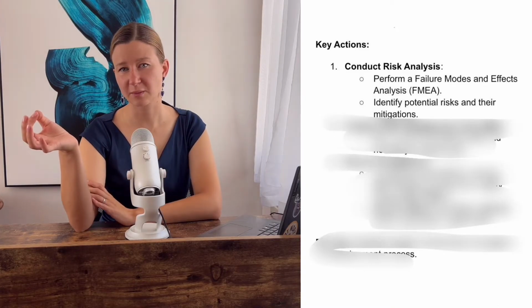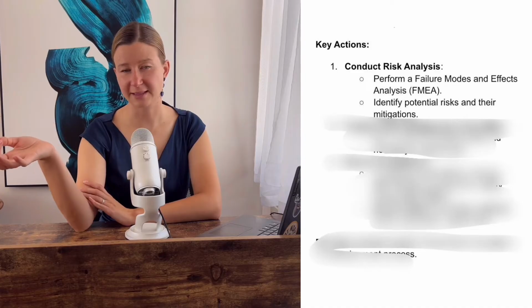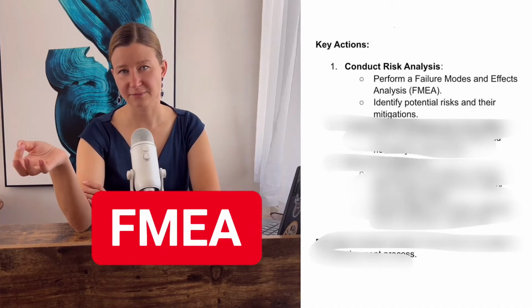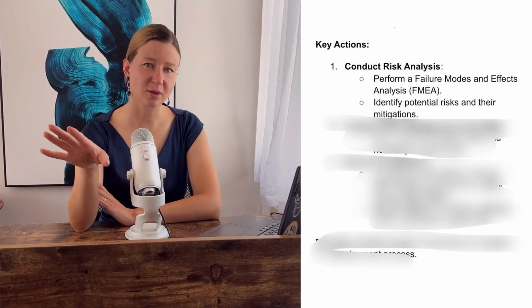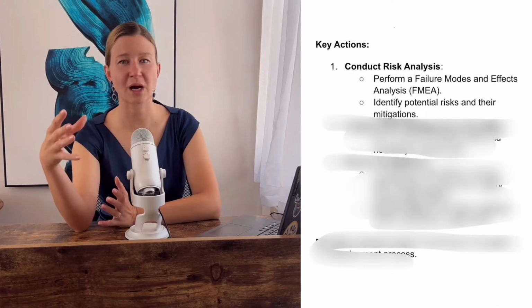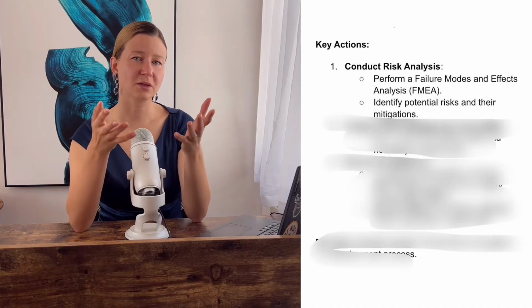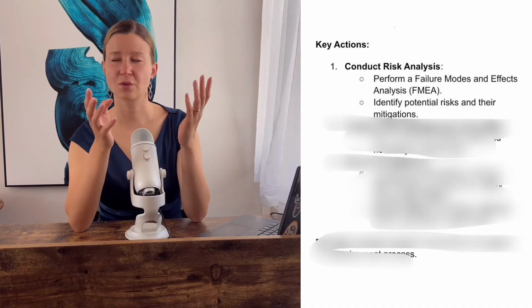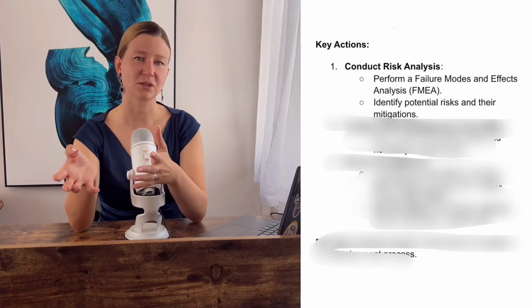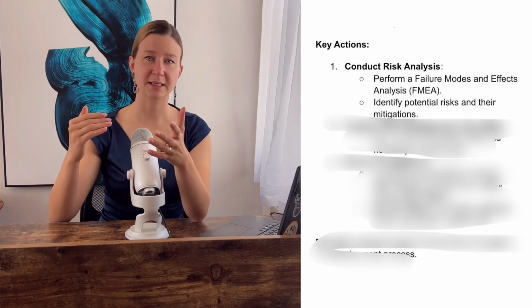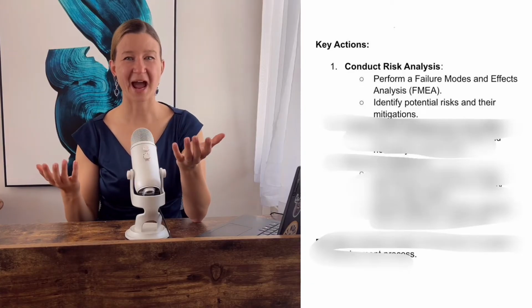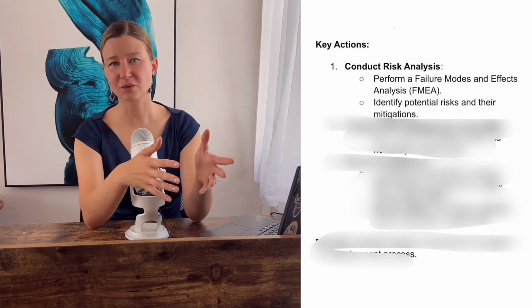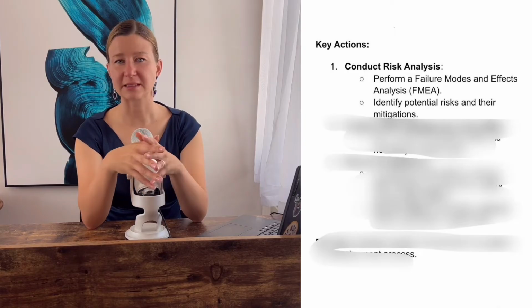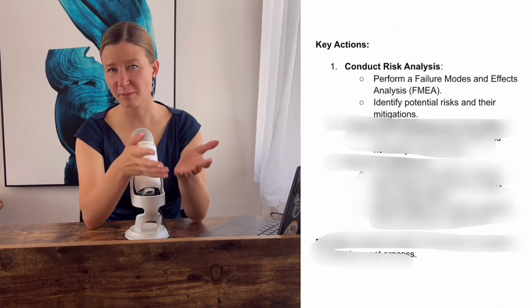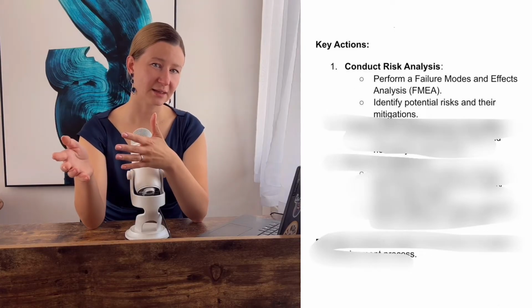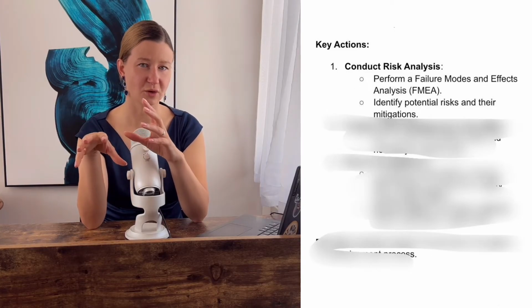So first you start with something called failure modes and effects analysis. Think of this as looking at every possible way your device could fail and figuring out how serious each problem could be. For example, could a software glitch cause the device to stop working? Could a part of the device break during use? Then you rank these problems based on how bad they might be and how likely they are to happen. For the most serious risks, you come up with a plan to prevent them. For instance, if a software malfunction could harm a patient, you might add extra safety checks in the code to catch any errors before they cause trouble.